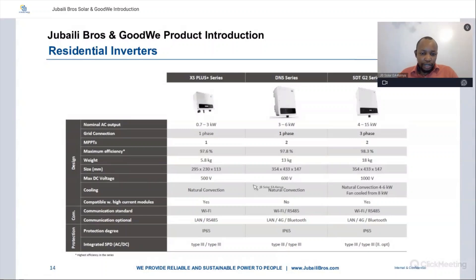Detailed information is available on the datasheets from the GoodWe website. Cooling is via natural convection for all single-phase units, and for the three-phase, natural convection from 4 to 6 kilowatts and fan-cooled for 8 kilowatts and above. Communication is Wi-Fi for the single-phase XS Plus, Wi-Fi and RS485 for the DNS, and the same for the SDT G2 series. All three categories have an IP65 protection rating and come with Type 2 or Type 3 surge protection devices.